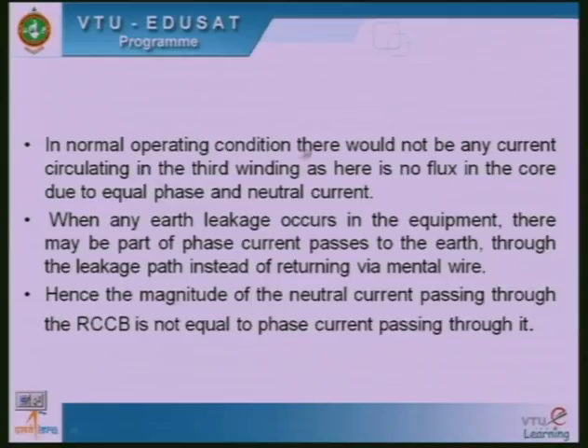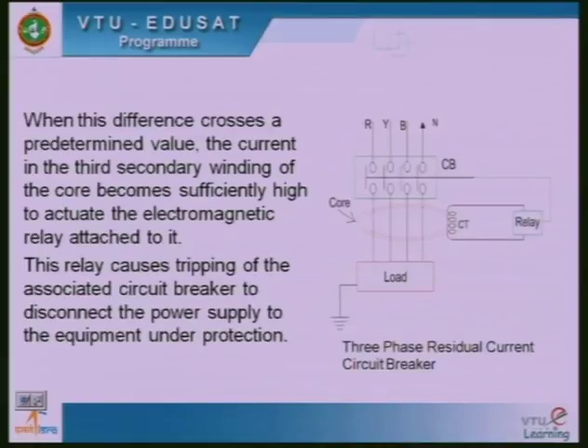In normal operating condition there won't be any current in the third winding, as there is no flux in the core due to equal phase and neutral current. Whenever a leakage occurs, this balance will get lost, therefore the relay will trip, causing the circuit to trip, okay. So this is normally the operation of an RCCB, residual current circuit breaker. We can have a 3-phase residual current circuit breaker or a single phase residual current circuit breaker. The operation is the same for both cases, okay.